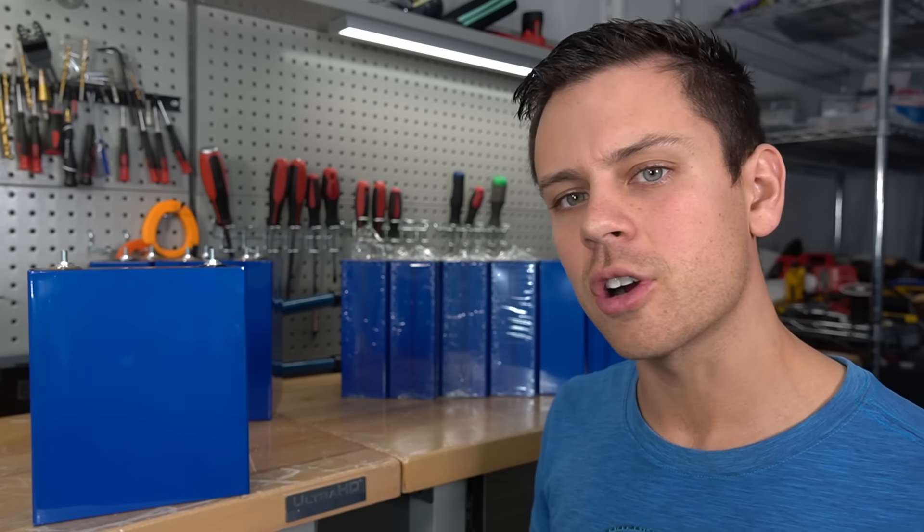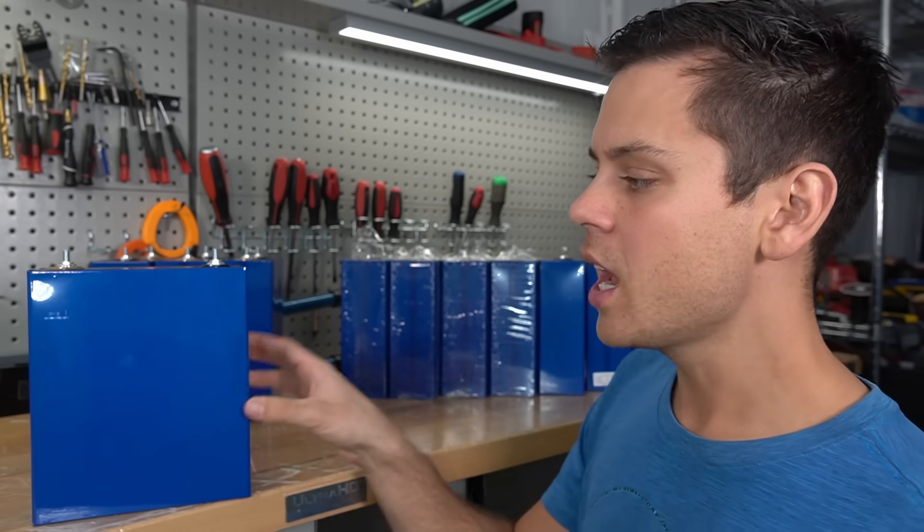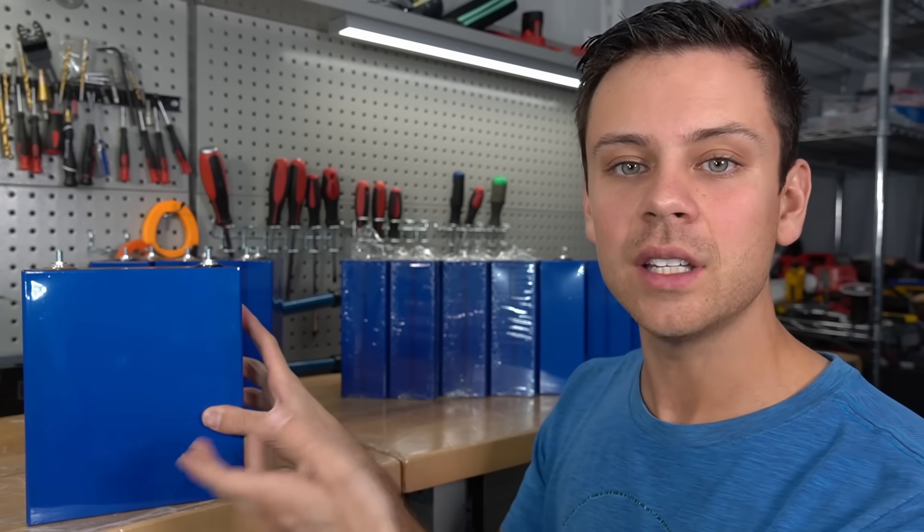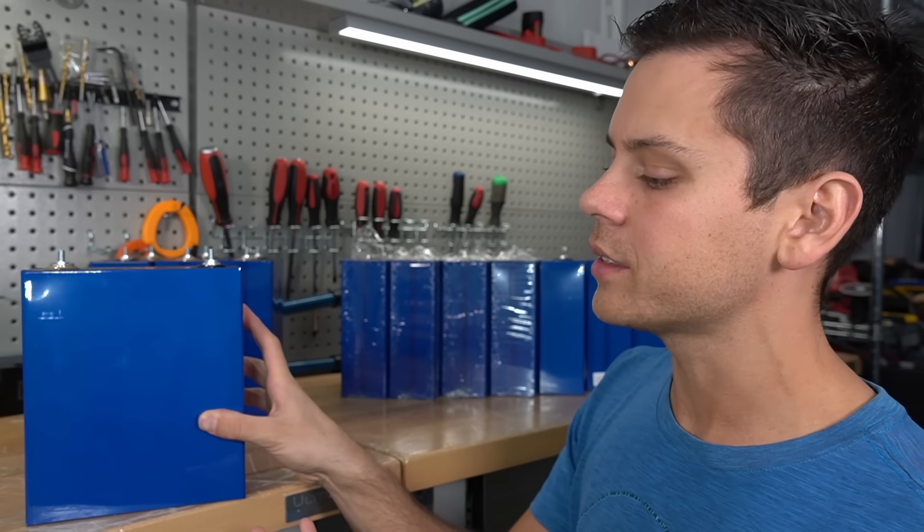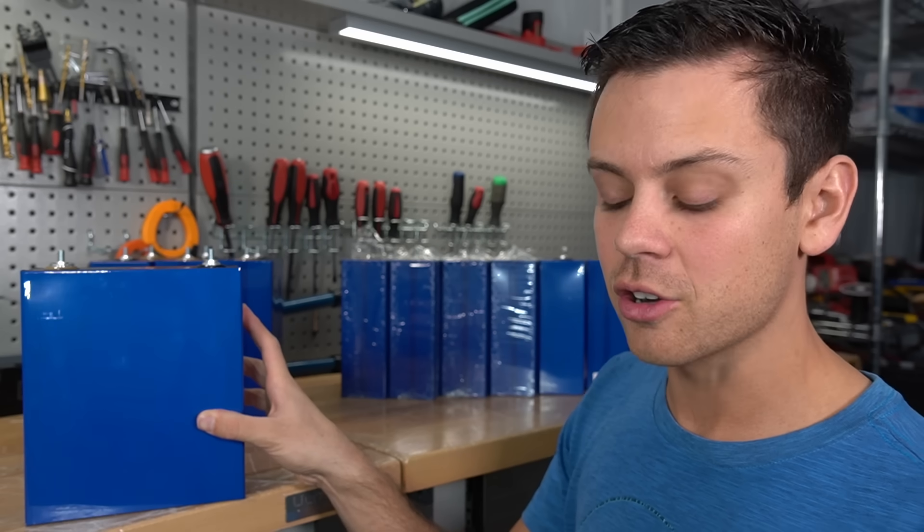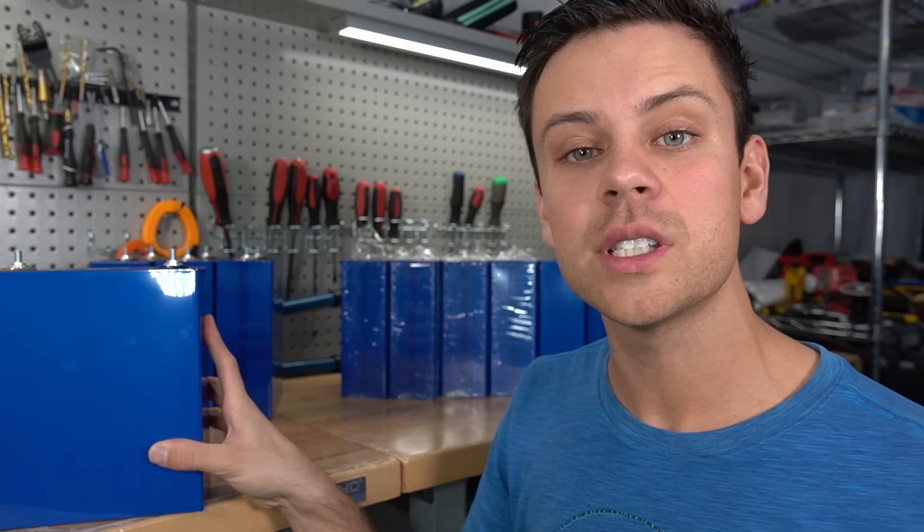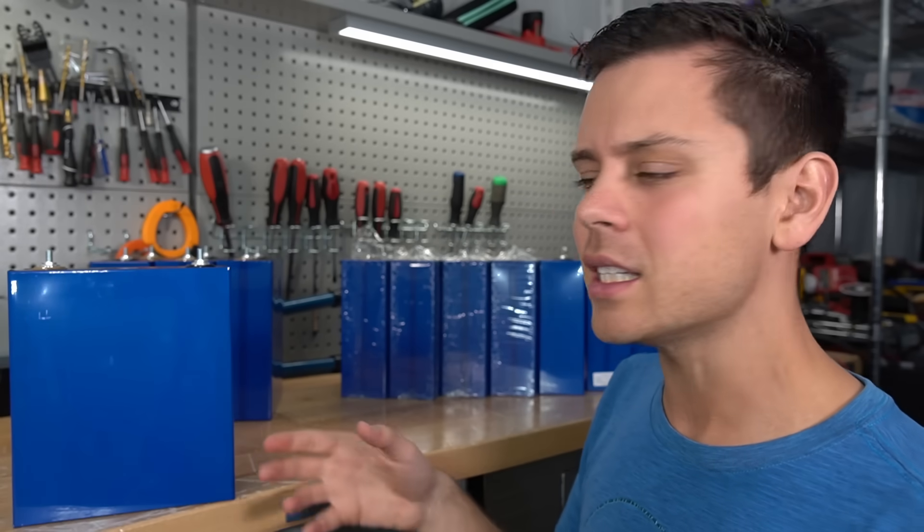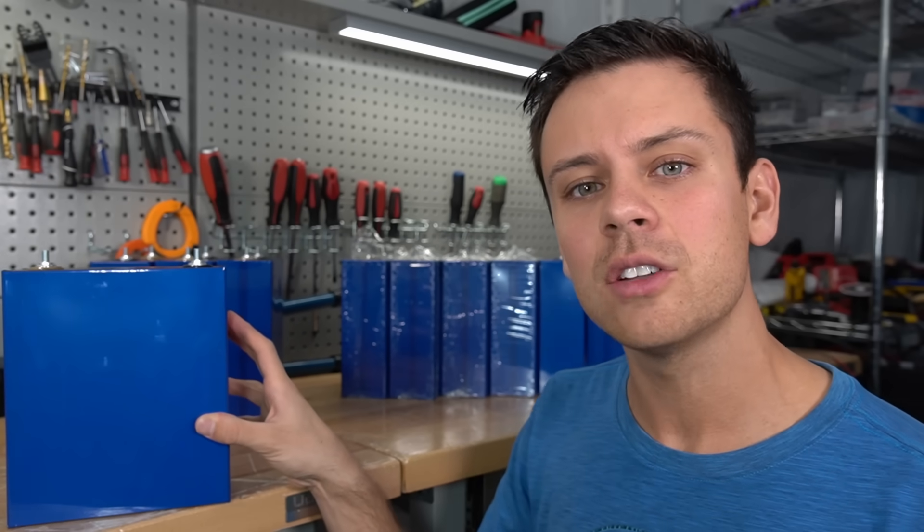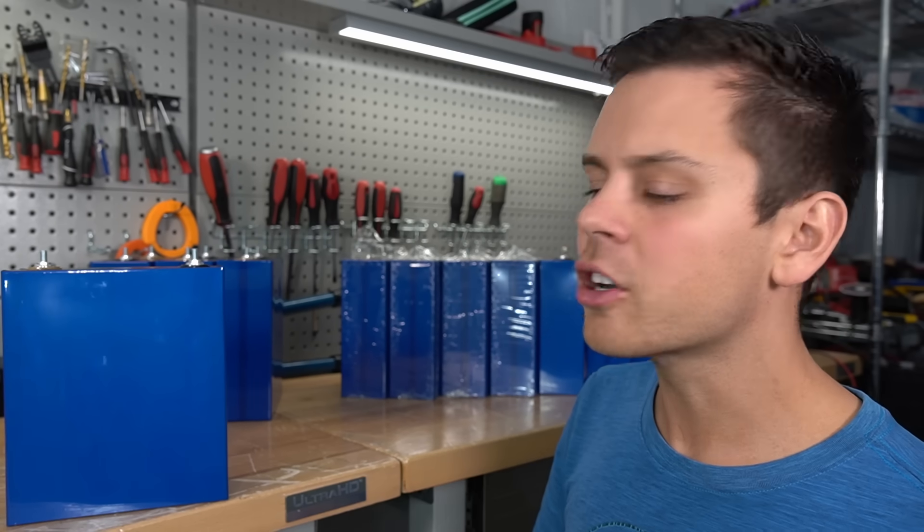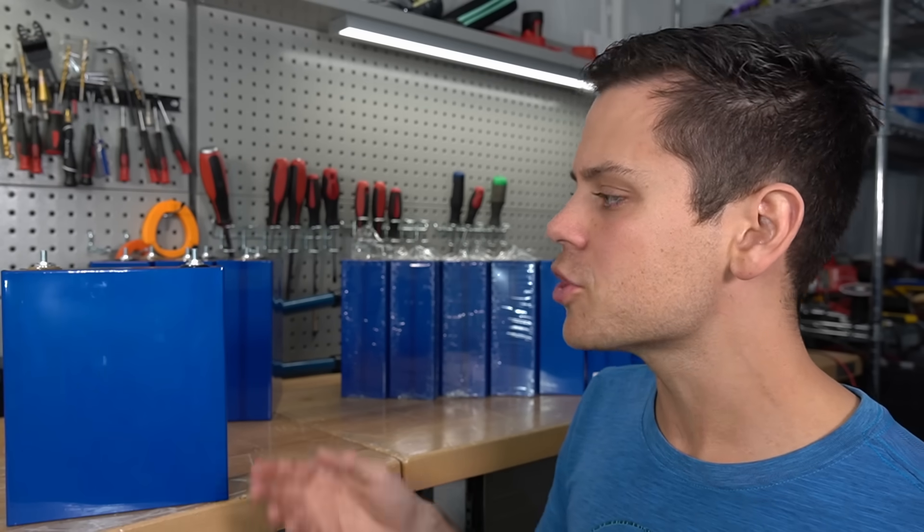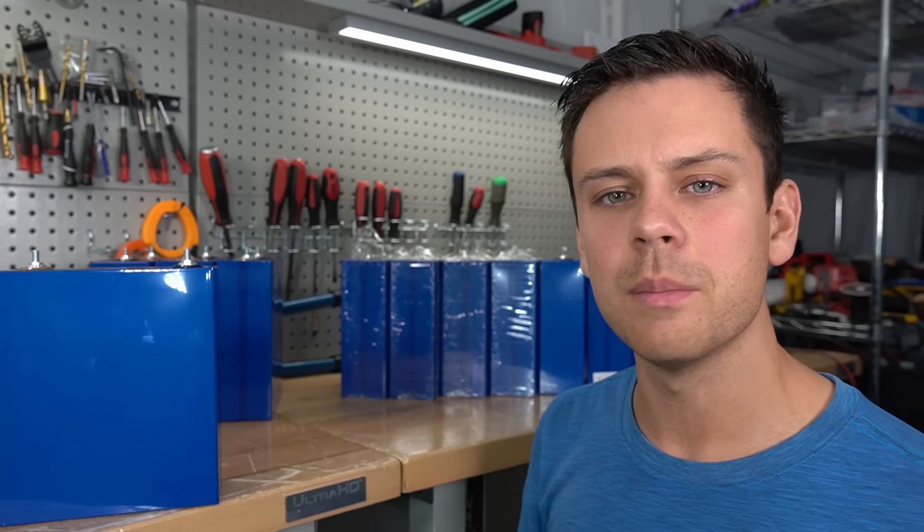I was looking at some of the data and I posted some of the literature on the forum. I think most people will kill these batteries through calendar aging before they will from cycling with solar, and that's because with solar you're charging and discharging at a lower C rate than other applications. These are designed for use in EVs and typically they have to run inductive loads with high surge capacity. People are charging and discharging a lot and very quickly with speed charging like a 2C rate sometimes.